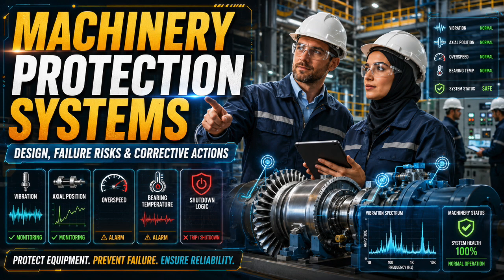That is why a good engineer does not only ask, what is the vibration value? A good engineer asks, can I trust this vibration value? Probe orientation matters. Probe gap matters. Probe tip clearance matters. Distance from bearing matters. Cable length matters. Oscillator to demodulator matching matters. Grounding matters. Runout matters. Field calibration matters. The display value is only the final number. The truth lives in the installation.